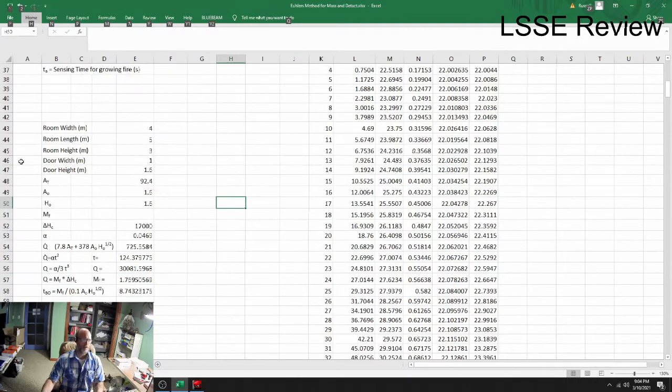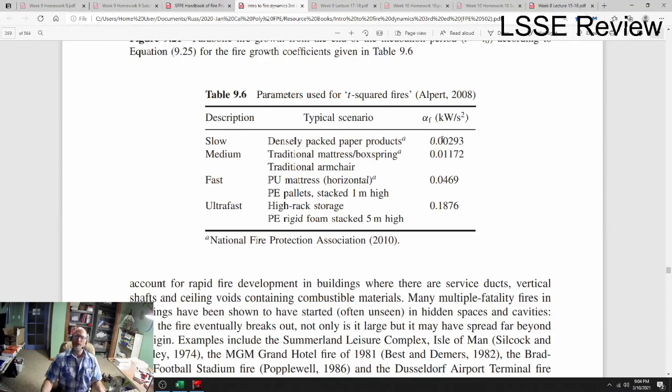So if you take a look, for instance, the common T-squared fire, which is defined by an alpha value. If you look at the alpha values, SFPE Handbook of Fire Protection Engineering has it. This is a Drysdale document here, but look at the significant figures you have on these values. And the reality is when you're trying to guess values, you're nowhere near 100,000th place. But these are standardized values. They represent pockets or themes associated with fire spread.